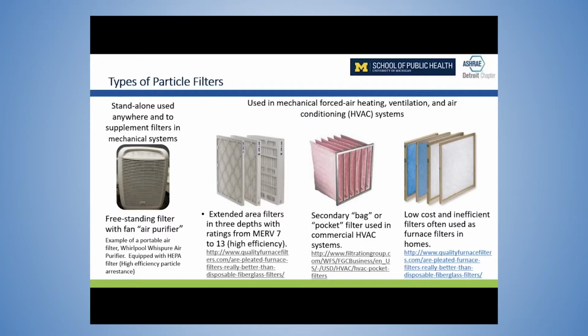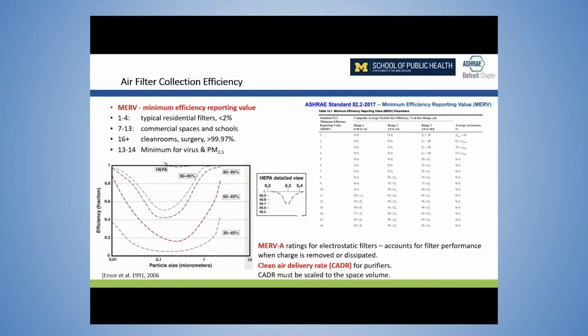So filter efficiency is rated using several different systems. Probably the most common is the minimum efficiency reporting value system, the MERV ratings. This is embodied in an ASHRAE code. I want to point out that when you get to smaller particles around the size of 0.5 to 1 micron, you can see how the filter efficiency drops in the case of all of these different lines here. These are the sizes of particles that are very important for PM 2.5 as well as for virus. Basically, a MERV filter under 11, 12, or 13 does very little for PM 2.5 or for the virus. So we really recommend a minimum MERV rating of 13 to address PM 2.5 and the virus.